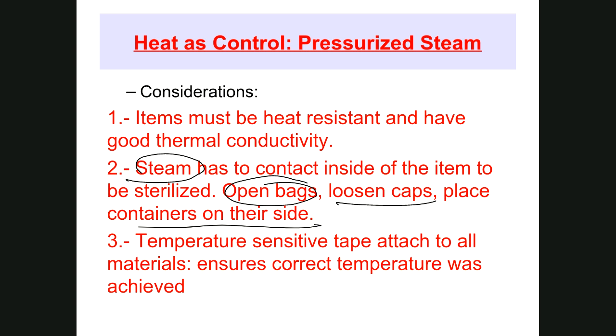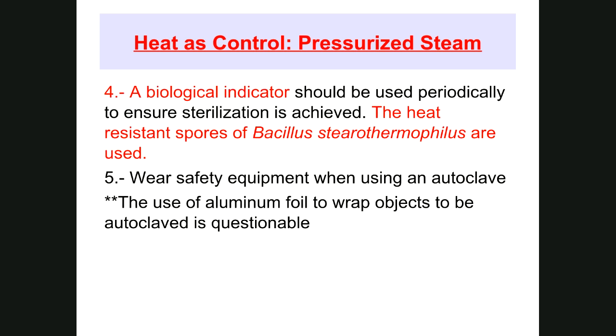Typically, there's a temperature-sensitive tape that is put on the object, and that tells you that the correct temperature has been achieved. It does not tell you if the object is sterile. It just tells you the right temperature was reached. We don't know anything about the pressure or whether the object is sterile, but we do know the temperature was reached. Yes, it changes color. Actually, typically what it does is that these lines appear through it. So it looks like regular tape, and then after autoclaving, it's the regular tape with these gray lines all through it. That tells you it's reached the correct temperature.